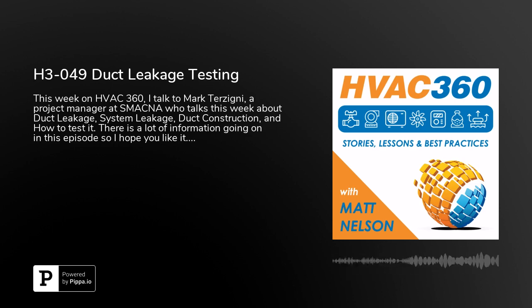For instance, ASHRAE 90.1 is an energy standard. We made a really big issue about saying, look, guys, we've gotten the duct to be pretty tight. Our research shows that it's pretty tight. It's sure it's not zero, and can we get it to zero? The answer is yes, it can be zero, but there's a certain cost involved in that. And what we're trying to do is get the industry aware of there's other lower hanging fruit right now. Let's bring the other components that make up a system, a distribution system for air, up to the standards of the duct, let's say, and then we can go back and say, okay, now let's go back and get the duct tighter if we can.